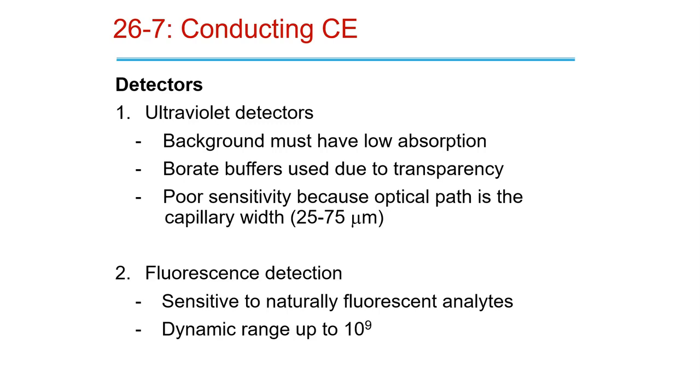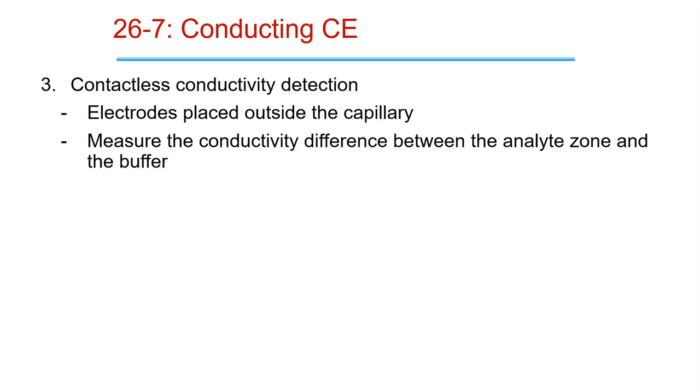And these detectors have gotten cheaper and cheaper because you're able to get this massive dynamic range, and it's just considered more standard. Even when you have to pay for it to get the additional fluorescence detector because UVs are still considered standard, the UV-Vis, it's absolutely worth the money because it's going to extend your range. It's going to really deal with your sensitivity issues.